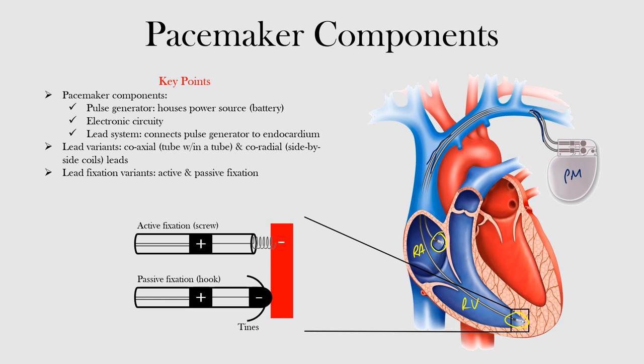Insulation materials separate the conductor cables and the lead tip electrodes. The leads can be designed as coaxial or co-radial, depending on the relationship between the cables. Coaxial leads consist of a tube within a tube, whereas co-radial leads consist of side-by-side coils.